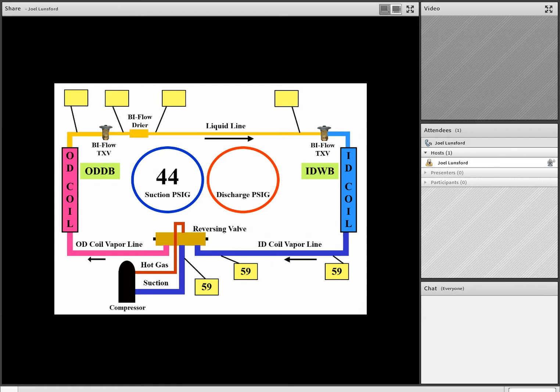In this example, we see we have 85 pounds of suction pressure, and we notice we have a pink or rose-colored background on the gauges, so we know it's an R410A call. So at 85 pounds of suction pressure, we see that we have a pressure temperature conversion off of our chart of about 24 degrees. The temperature leaving on the coil vapor line from the indoor coil, which is the cold coil in the cooling mode, is 54 degrees. It even goes up to 55 before it enters the reversing valve. So we'll just take the average and just say it's about 55 to 54 degrees.